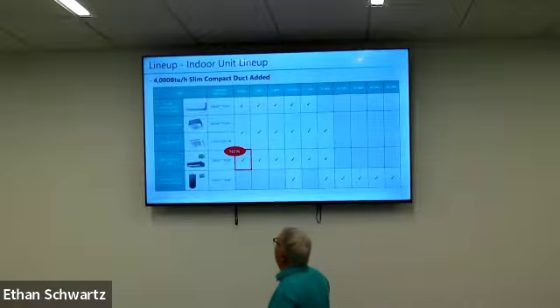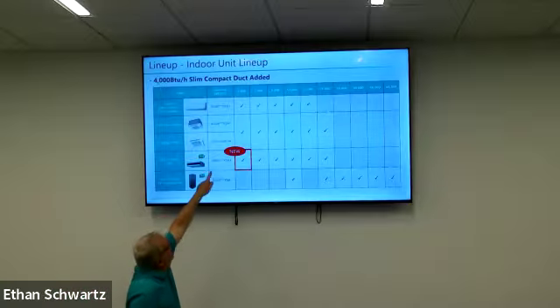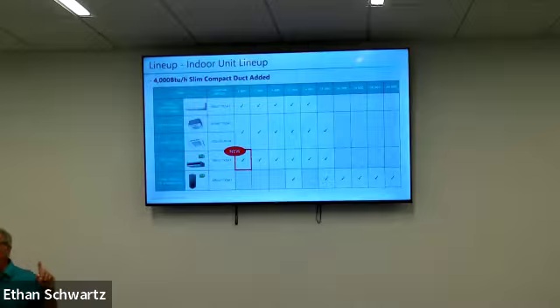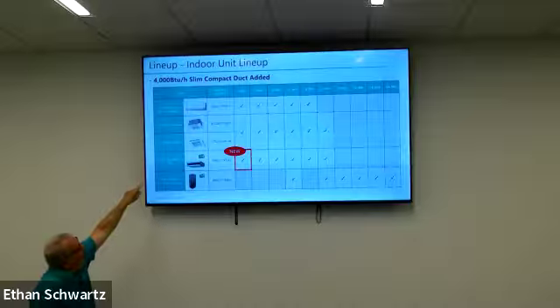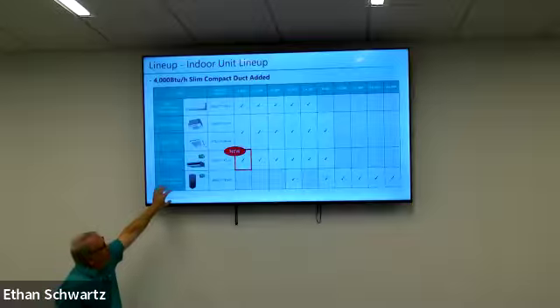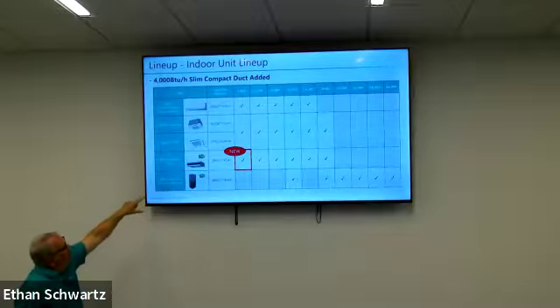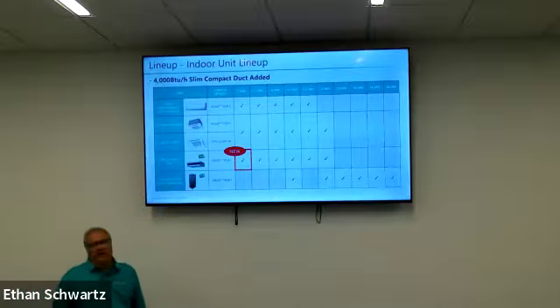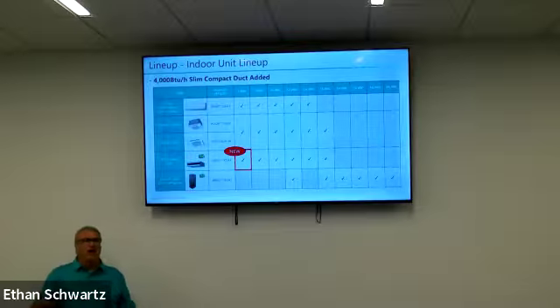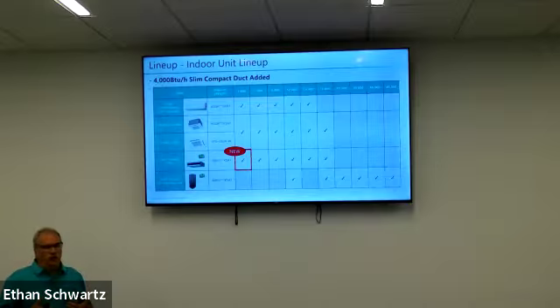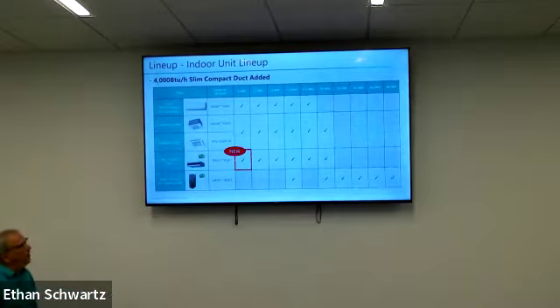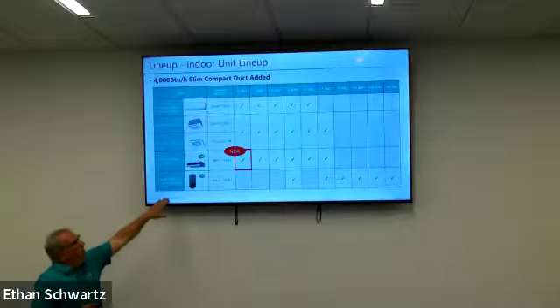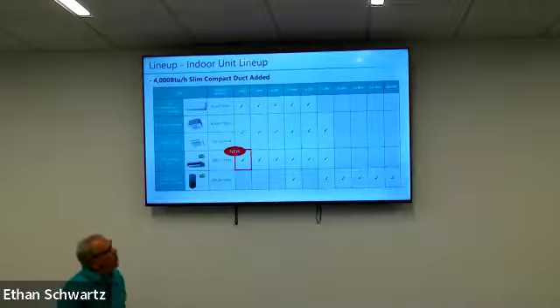So this is our indoor unit lineup. And you can see right here, we've got 4,000 BTUs. So that 2-ton becomes a very viable option. It's R32. So I'm going to show you something here you've probably already seen on the slide. But we're going to have the cassette, wall mount. These are all available right now. This is now just coming out. And then our ducted units are going to have the leak detection sensor built in, because in the calculation of applying R32 A2L refrigerants, the duct size and all of that comes into play as volume. And so Fujitsu on our ducted units has added the leak detection sensor.